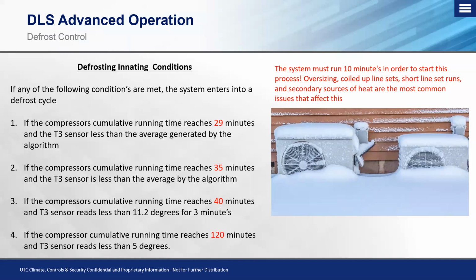Okay, if the compressor's cumulative runtime reaches 35 minutes and the T3 sensor is less than the average generated by the algorithm. So just like the first time, if for some odd reason that T3 sensor isn't below that threshold or that average generated by the set of rules or the algorithm on the outdoor board, or in layman's terms, that hasn't dropped below a certain degree yet, the compressor's runtime is going to reach 35 minutes. We're going to let that system run a little bit longer, see if we can get that temperature to go down on the outdoor coil so that we can initiate a defrost.